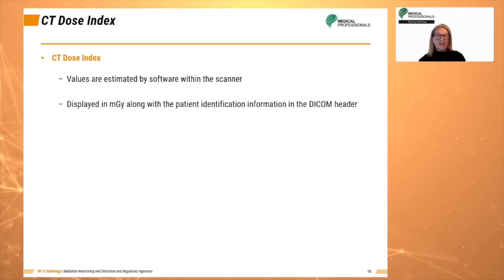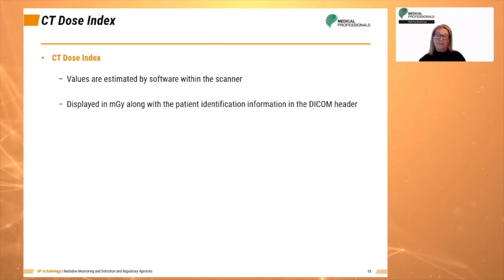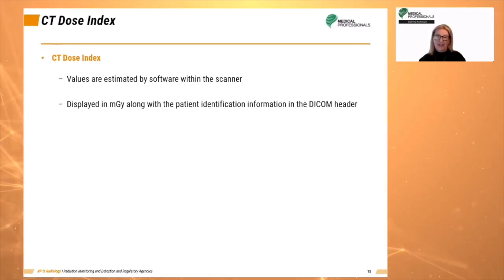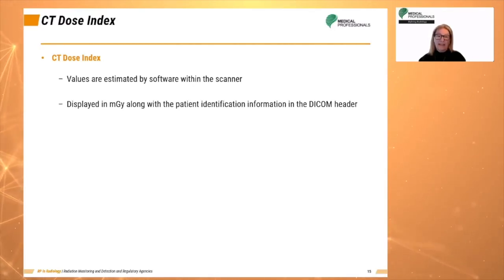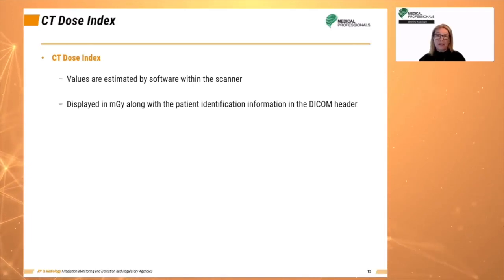CTDI is measured by the manufacturer and checked by the on-site physicist using an ionization chamber. Because the ionization chamber measures the exposure and not the dose, we convert Röntgens to milligrays. The volume CTDI, which is a derivative of the CTDI, can be used to express the average dose delivered to the scan volume for a specific examination. DLP, or dose length product, is the volume CTDI multiplied by the scan length in centimeters, given in units of milligray centimeters.